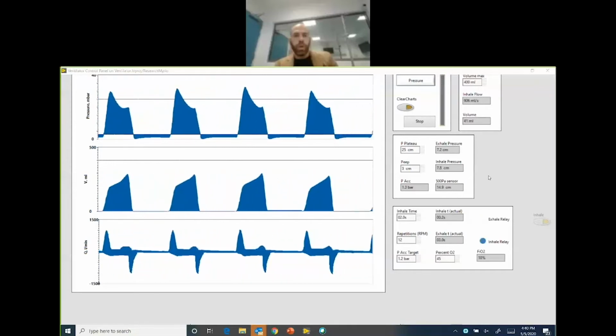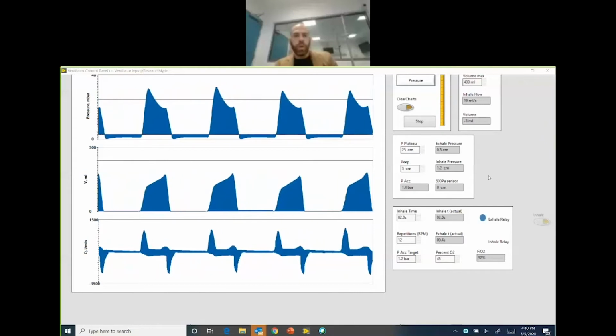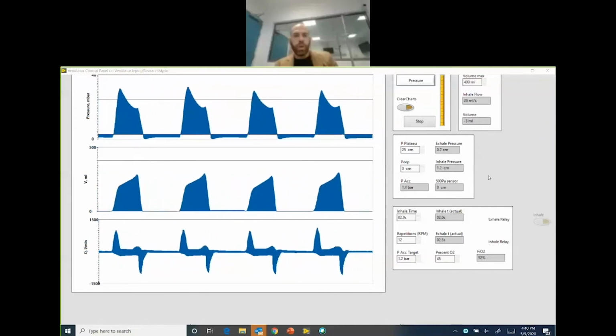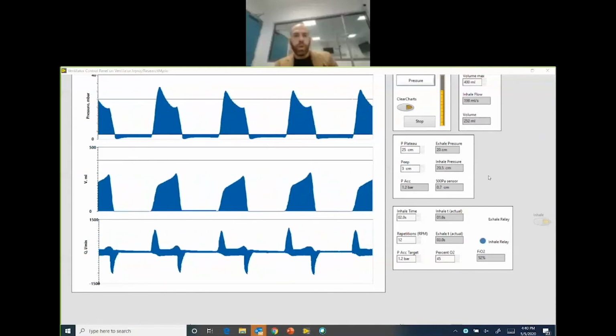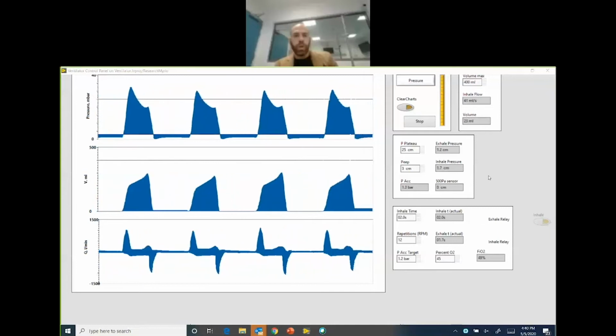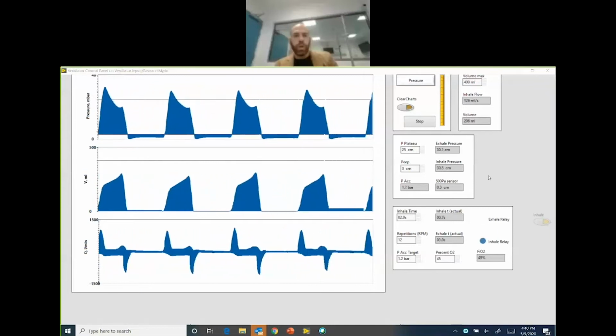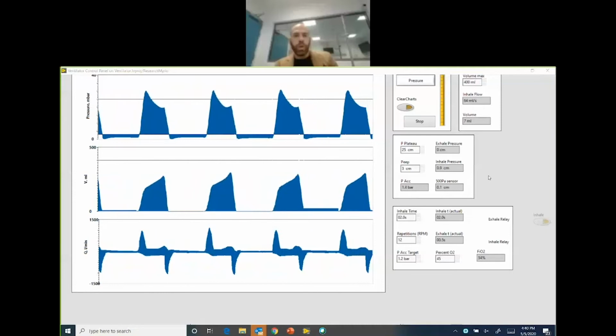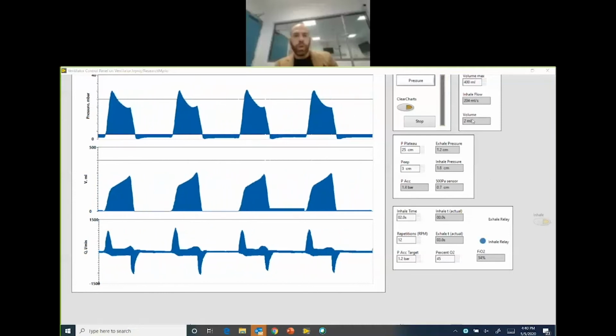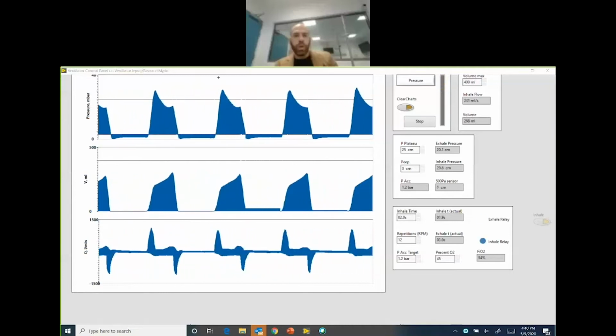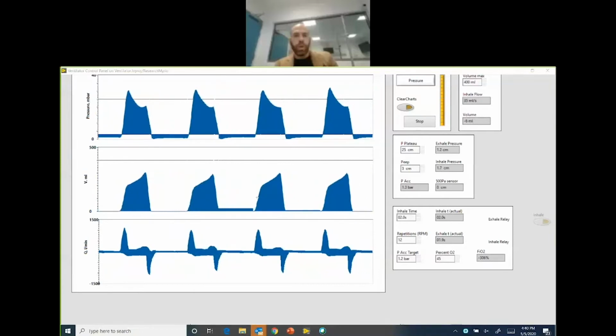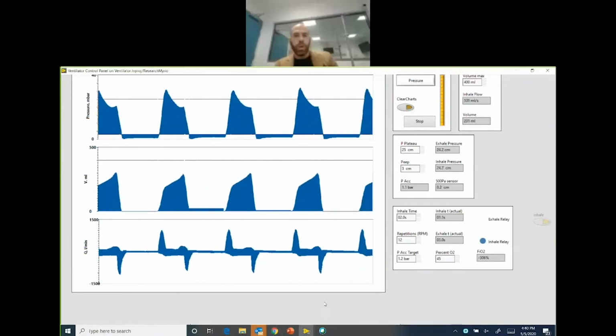This valve, which is normally open, which means even if you shut down everything, will have an integrated connector to it, so that you could add a manual ambu bag. So if you want to move the patient, if there is a reason for that, there is also no problem, without having to completely disconnect the machine. We also have a pressure relief valve. This is a mechanical pressure relief valve. It is required. It has to be there.